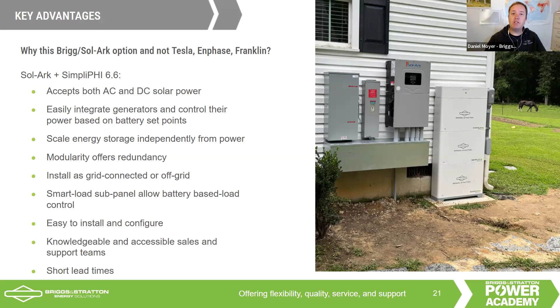This is an example of us going out to a site with a couple of Solar Edge inverters. We're bringing those Solar Edge inverters into a combiner panel, combining up their outputs, and feeding that into the Sol-Ark on the gen port. As far as the Sol-Ark is concerned, it's just more AC coming in. That AC can be used to support the home loads, to charge the batteries, and if it exceeds both of those, it can still be sent back out to the grid.